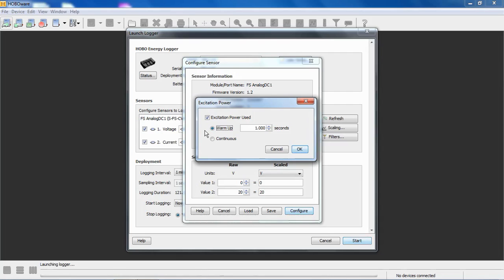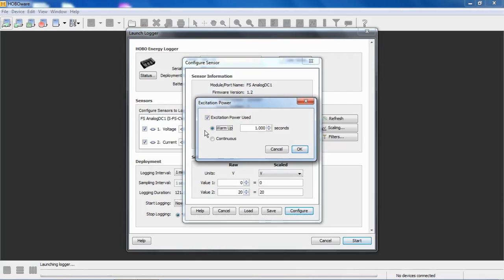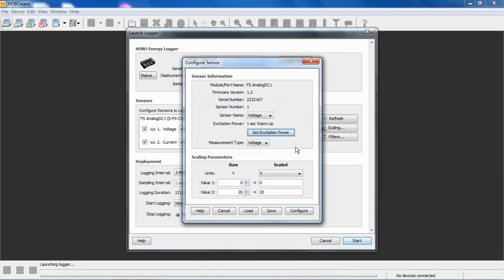This particular logger has an optional AC power supply, a wall wart, that plugs into the wall. So if you're using that power supply, you can use continuous power, select continuous power, and not pay a penalty in battery life because you're running off the AC. If you are running off batteries, it's strongly recommended to use the warm-up time. It will really help save on your battery life. So if we're happy with this configuration, we click OK.